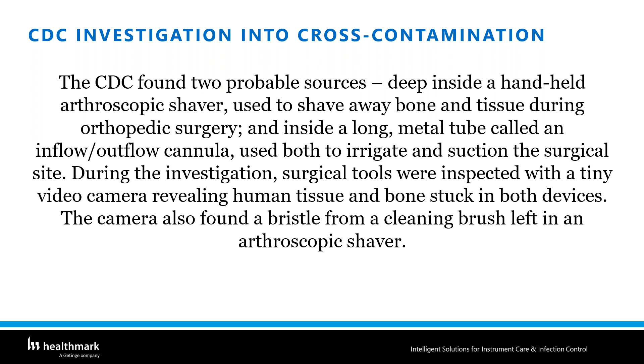Since this is a medical device, CDC pushed it to FDA, their sister agency, to look into it a little more. FDA sent a letter to all the hospitals saying that FDA became aware of cases in which tissue remained inside the arthroscopic shaver, and that you need to look at your IFU and make sure the devices are clean. FDA said the reports suggest the retained tissue was not evident to the naked eye, and multiple manufacturers sent letters to their customers to look into that. That was in 2009, but it took several years.